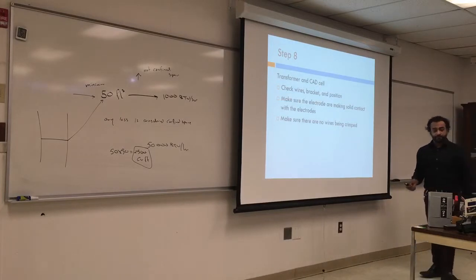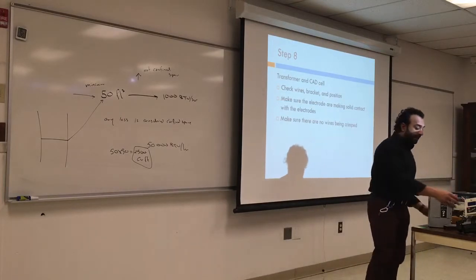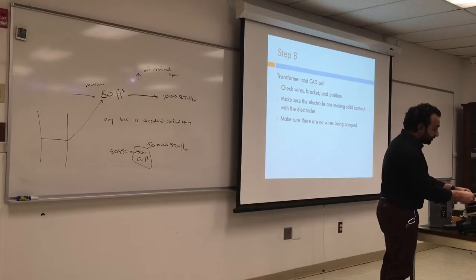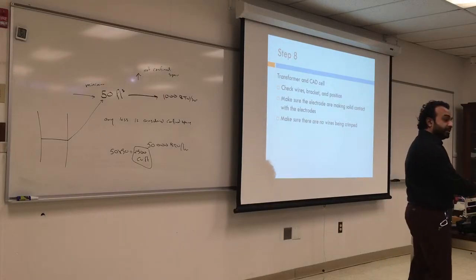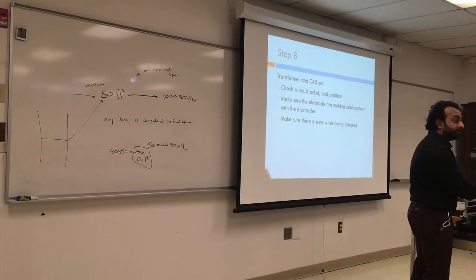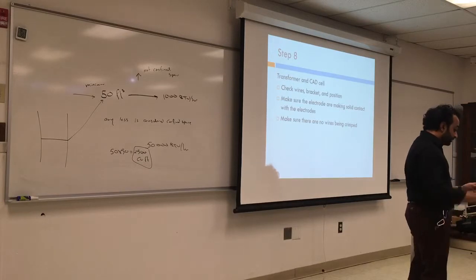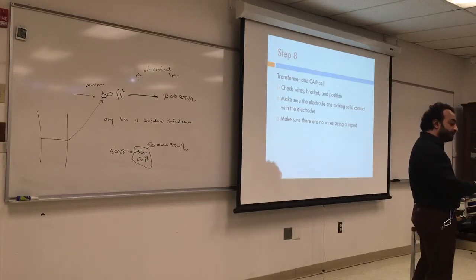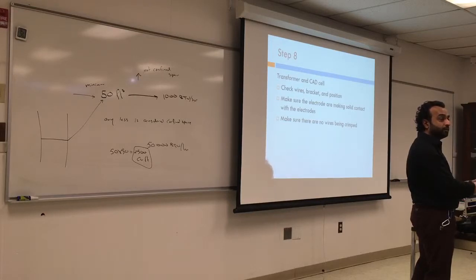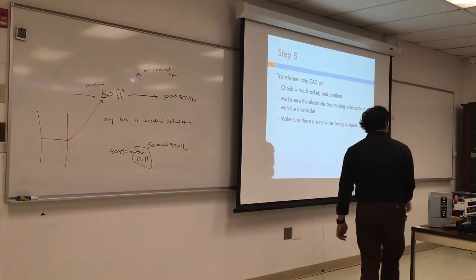Wires should not be crimped. Again, never be pleased with just cutting things in when wires are not connected very well. When you put the control back in the junction box, make sure it's not touching the junction box. Make sure that there are no exposed wires between the sleeve connection and the wire. I've seen that a lot. You get more than you're supposed to, and there's a lot of exposed wire. That's an accident waiting to happen. Make sure all the wires are completely covered and sheathed.